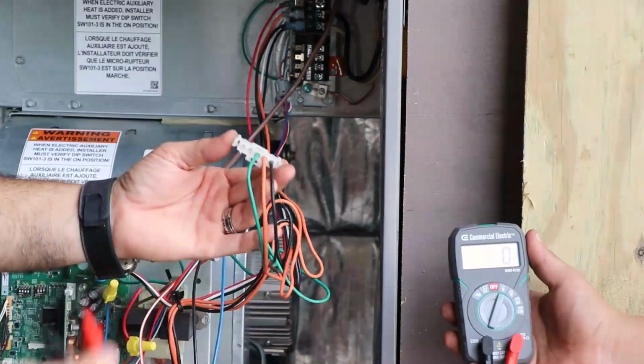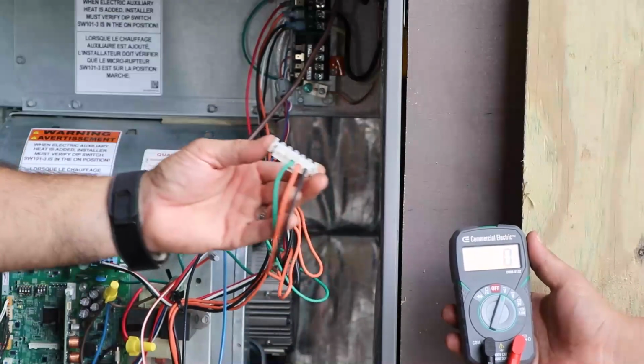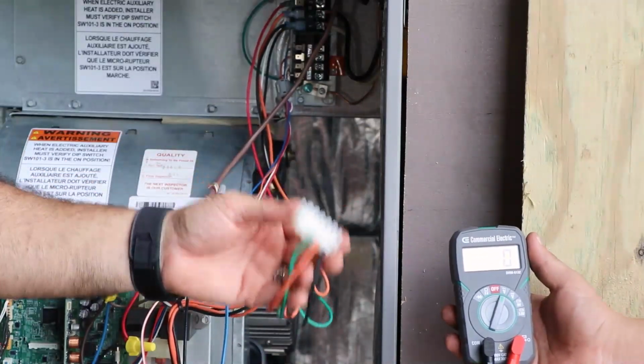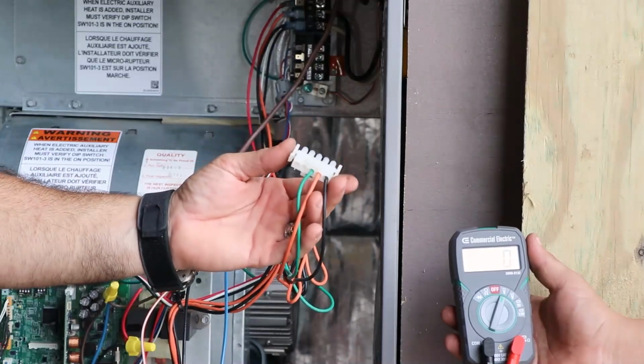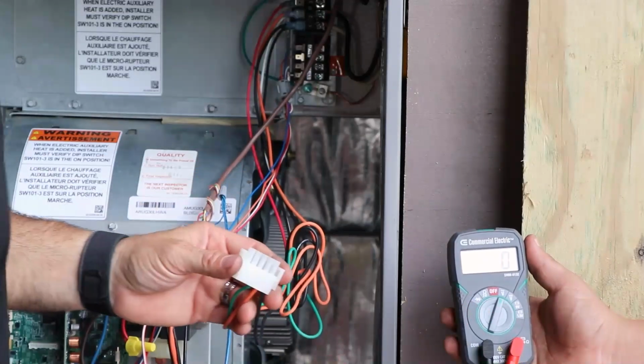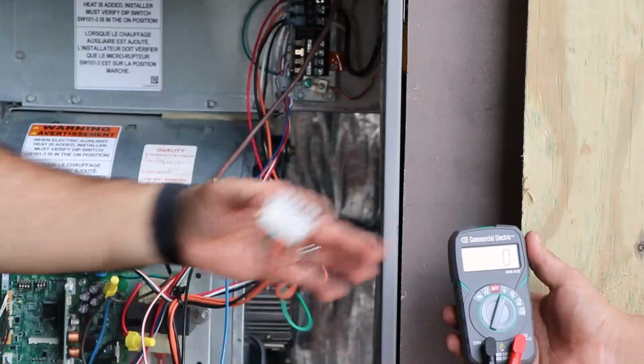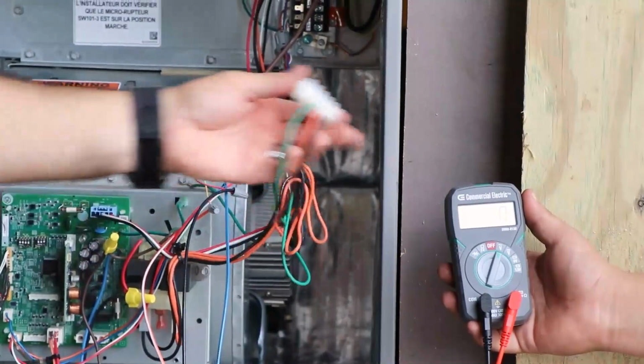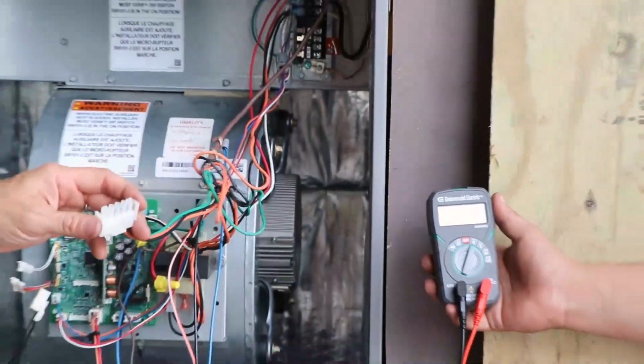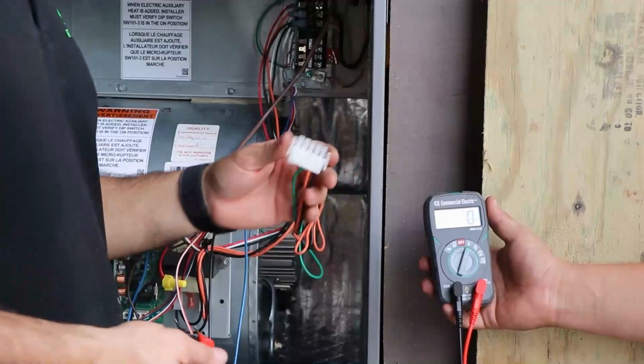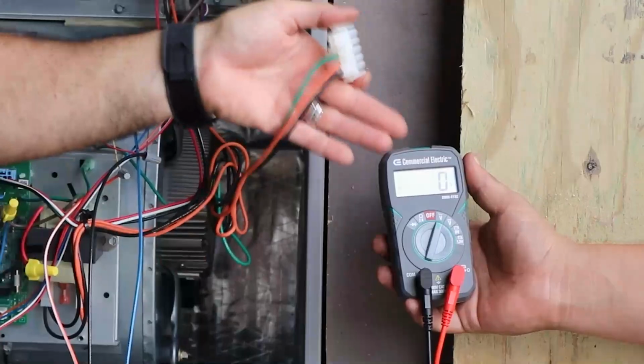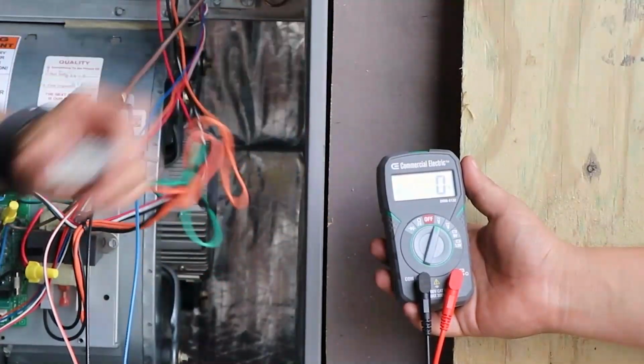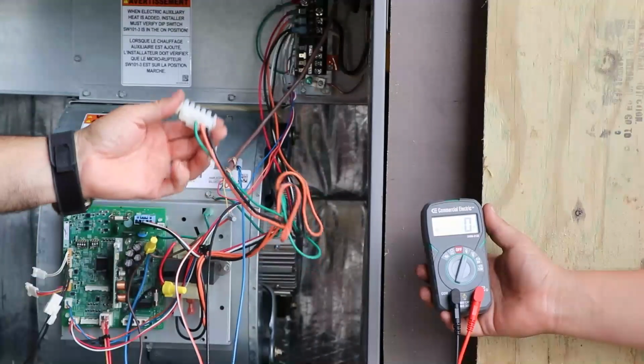Now, some of you are going to have 110 connectors, and some are going to have 220. So I'm going to go over first how you test a 110. When you have a 110, your multimeter is going to be in voltage AC, and go ahead and pick a scale that will allow you to test up to 220 volts. On your voltmeter, it may actually be a 600 scale. On this particular multimeter, it auto-selects, so we don't have to worry about what scale we're in.